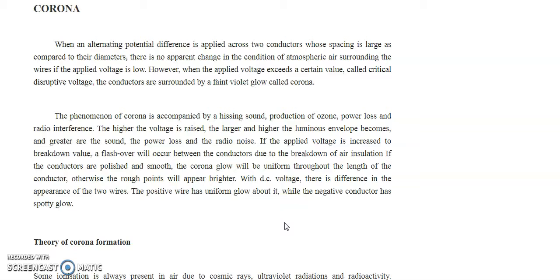This corona is related to our transmission line, and the main thing is, whenever you apply a certain amount of potential across two conductors with some spacing, there is no apparent change you can visualize. But when you increase the voltage to some extent, and we will call that voltage the critical disruptive voltage, beyond that level you can see a faint violet glowing nature, which we call corona, right?